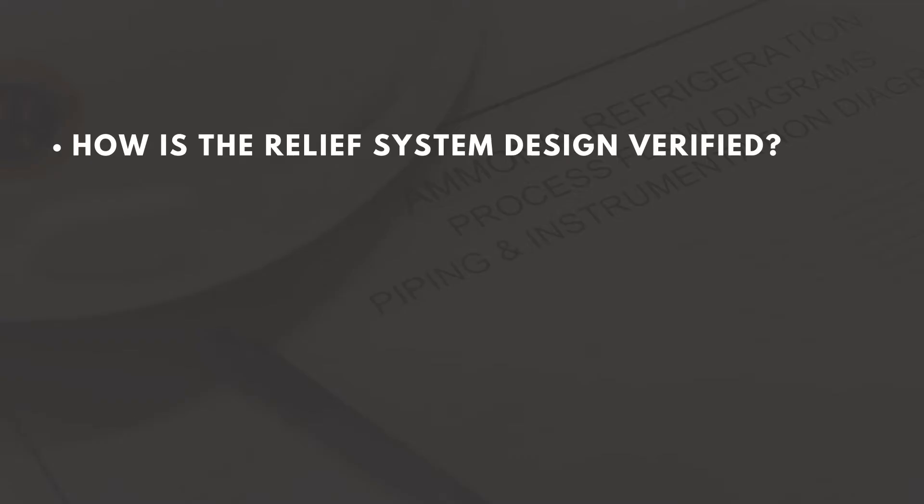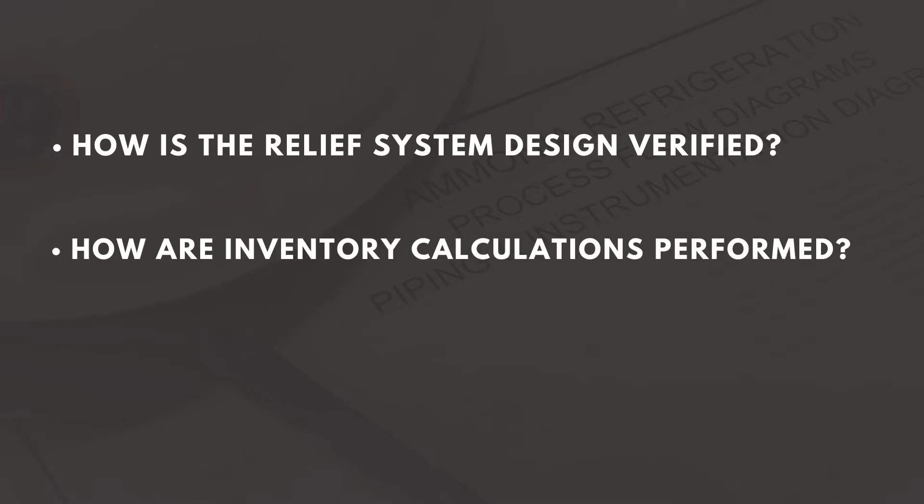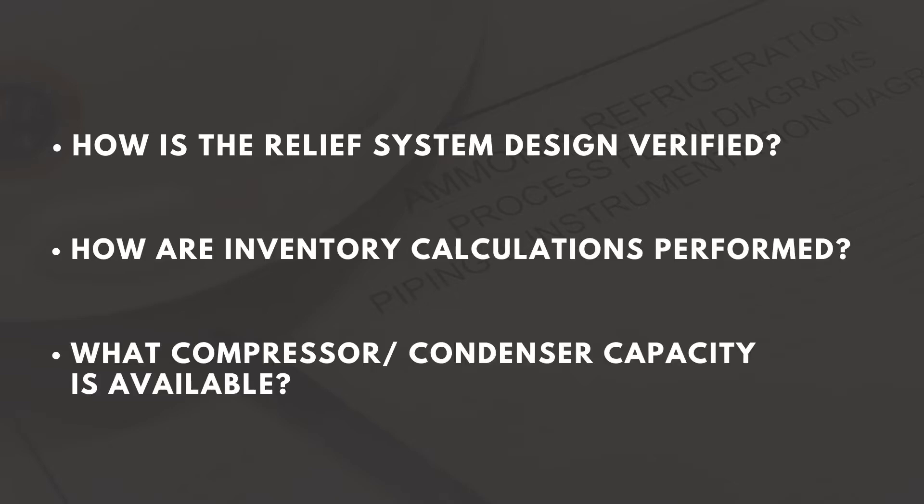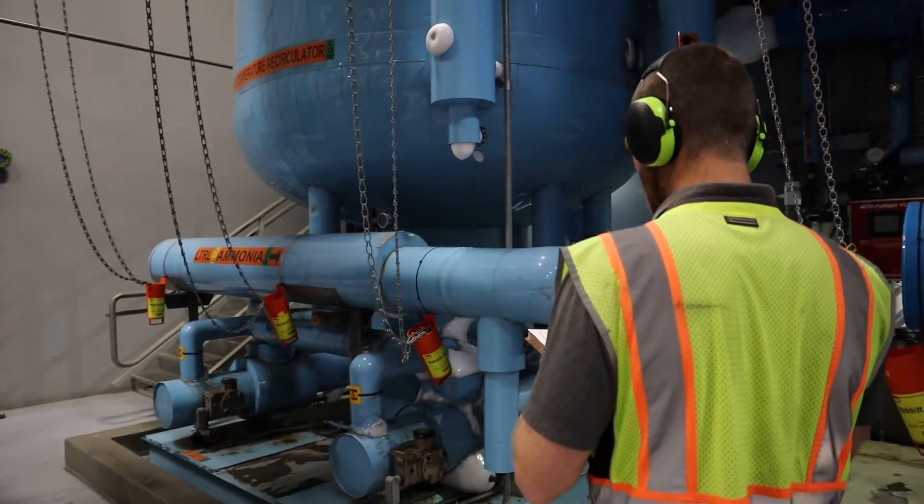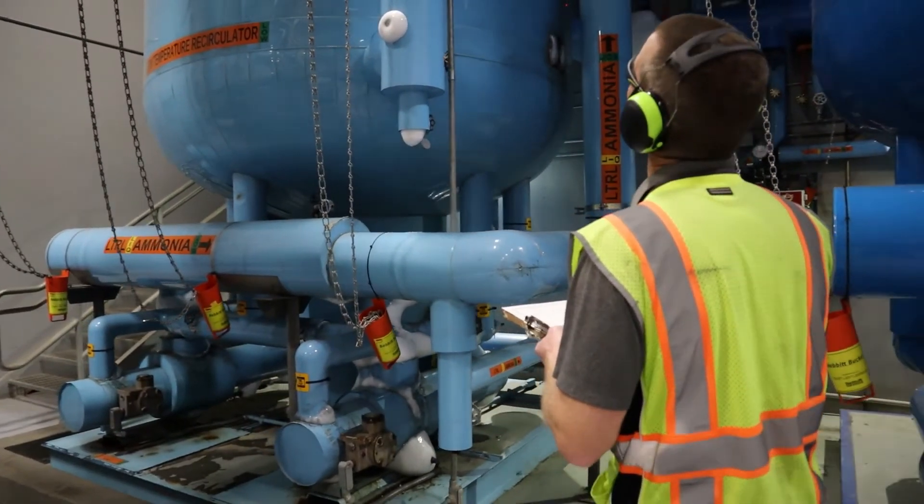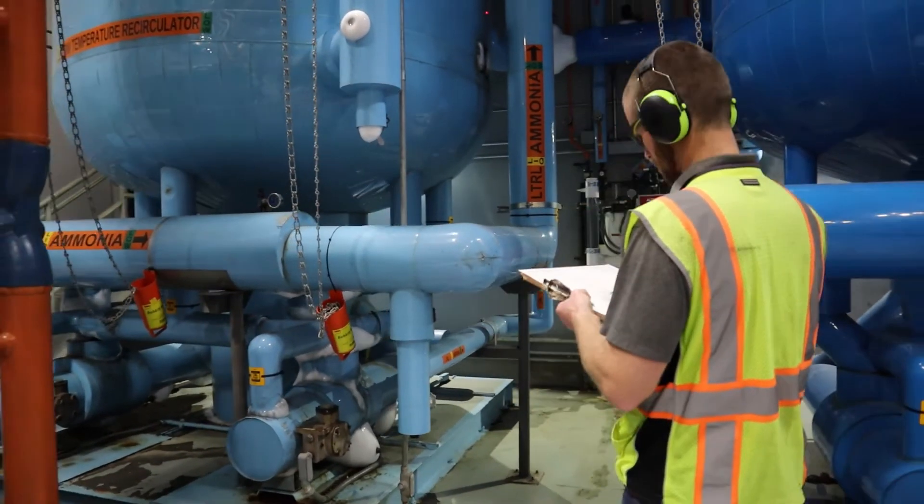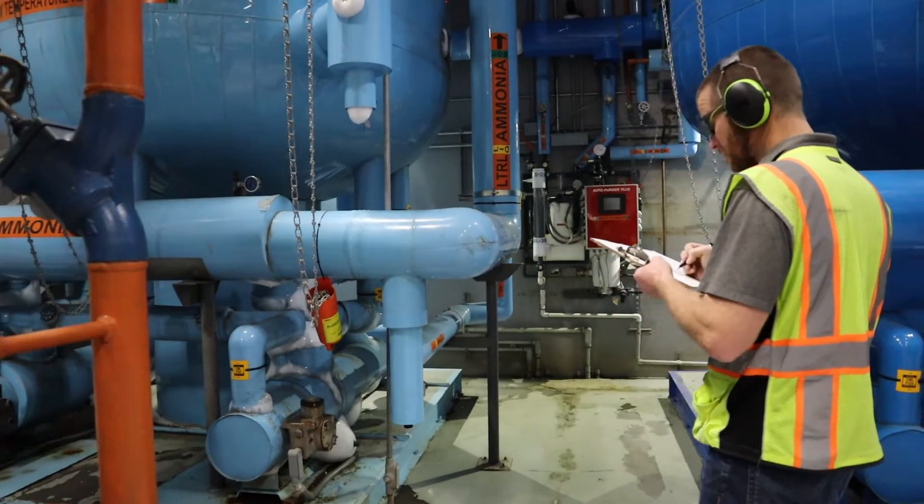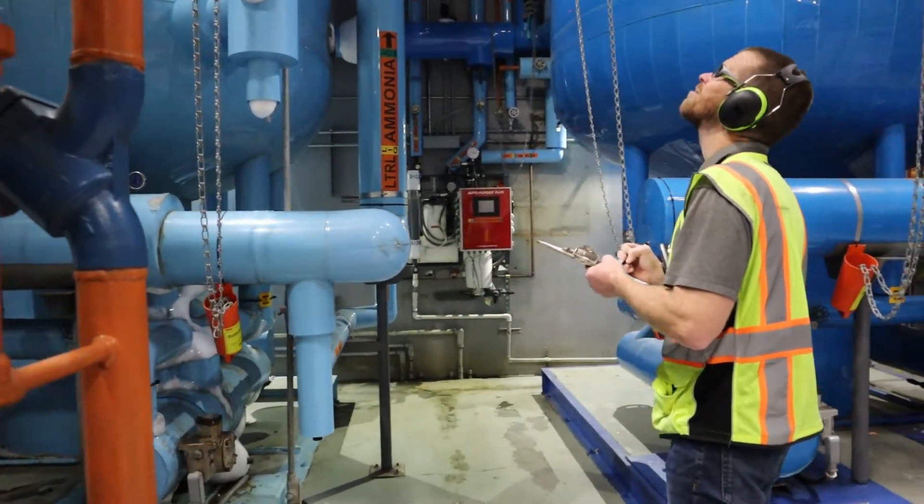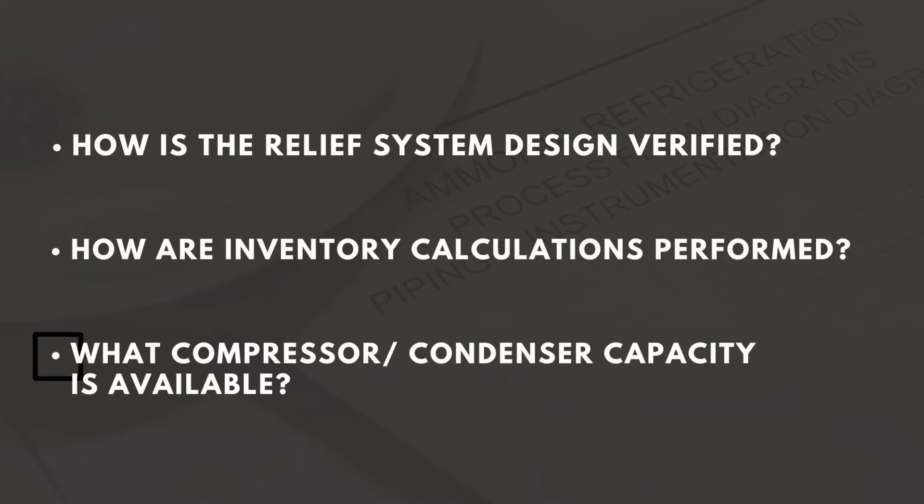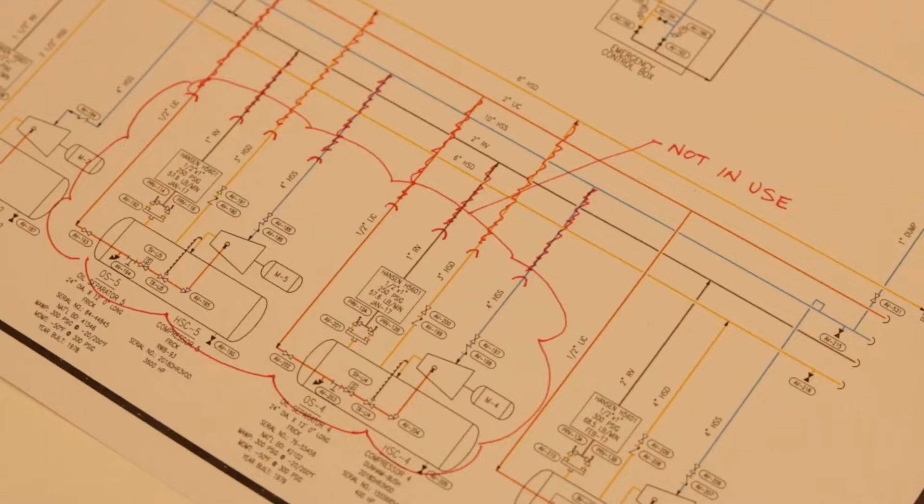How is the relief system design verified? How are inventory calculations performed? What compressor condenser capacity is available? Oftentimes, these questions can be answered in part by examining the P&IDs. If your system P&IDs are accurate, there is a high likelihood that your process safety information will be in good shape. On the other hand, if P&IDs are incorrect, process safety information is almost guaranteed to be riddled with inconsistencies.